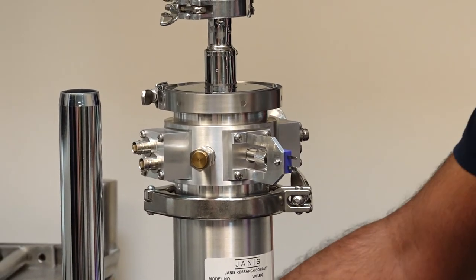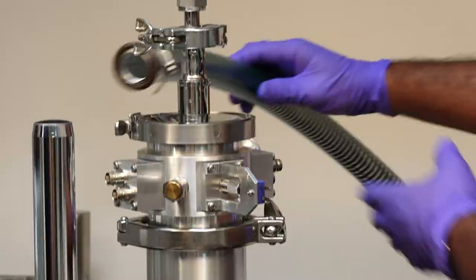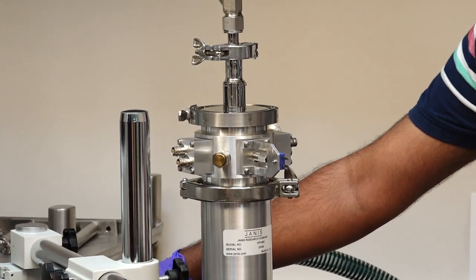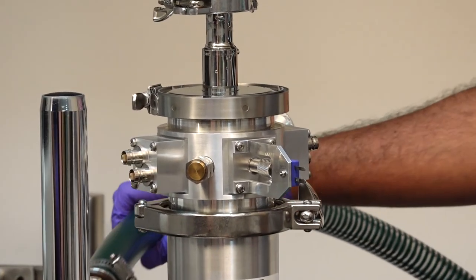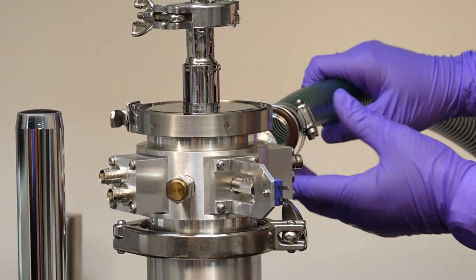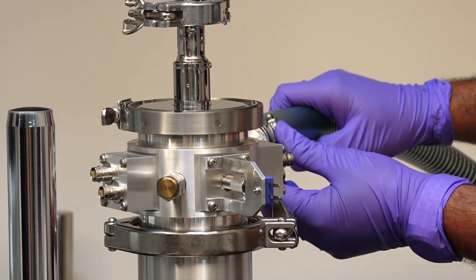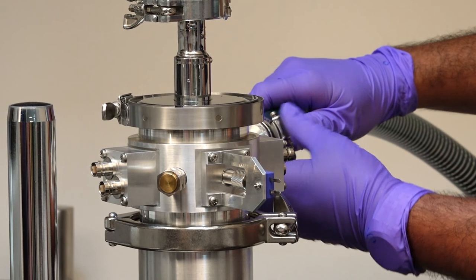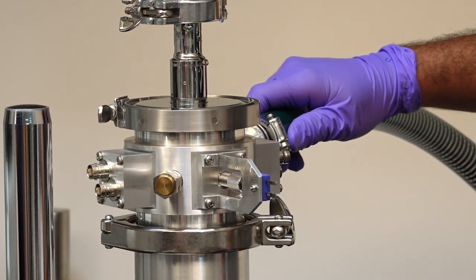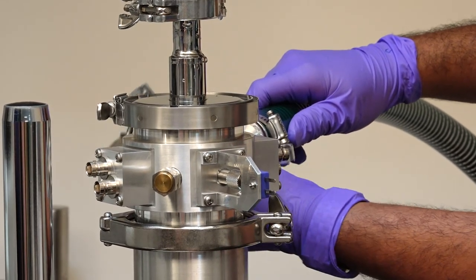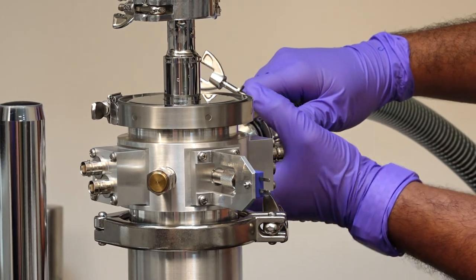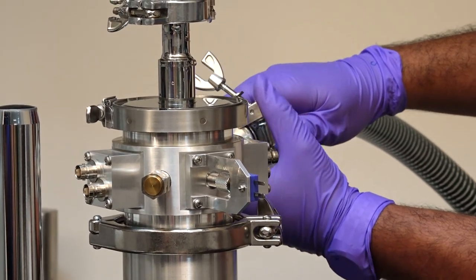Once that is tightened, we now connect the turbo pump. Once the KF flange is tightened, we'll put in the connections to the turbo pump, as you can see, with these specialized cables. The pipe is being connected using another flange.